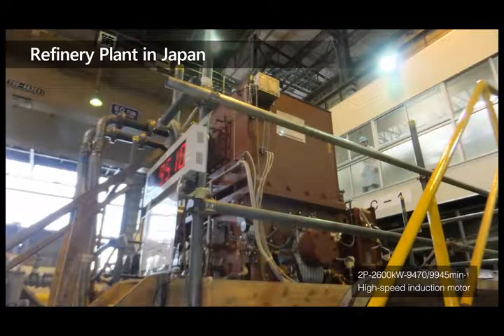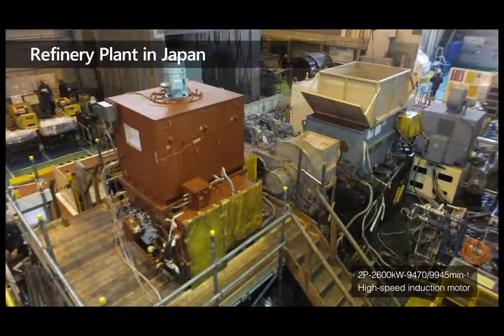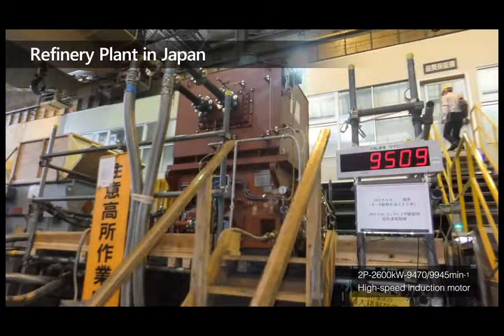Another gas turbine replacement was for a refinery plant in Japan. The customer intended to maximize their plant efficiency to save energy. The driver was a 2,600 kilowatt induction motor with a speed of 9,470 rotations per minute.